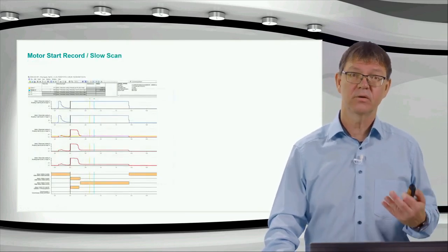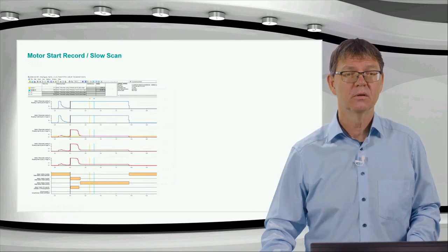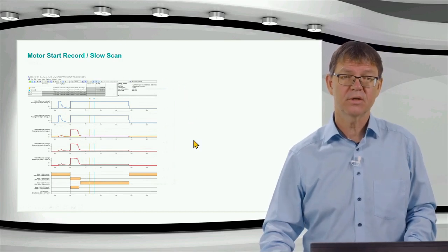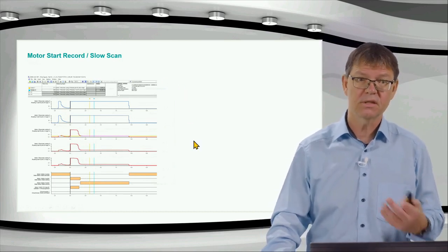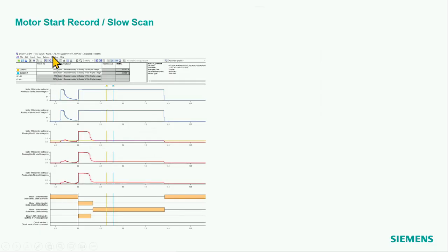Okay, this is how it looks when you watch such a start record with the SIGRA, for example. Then I have here the voltages. One voltage is now missing because I wanted to show the binary traces and the three currents. And this is a special switchover of a motor, which I had as a COMTRADE file, which I run on the digital twin.